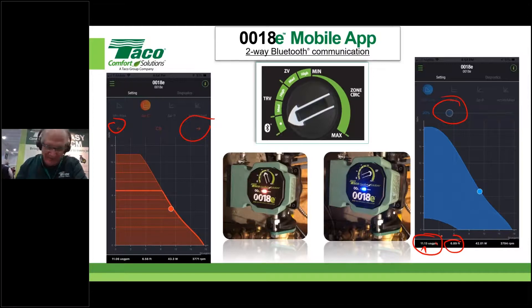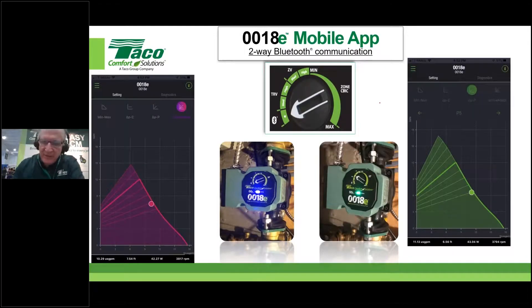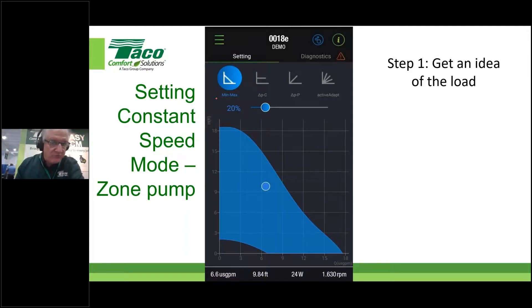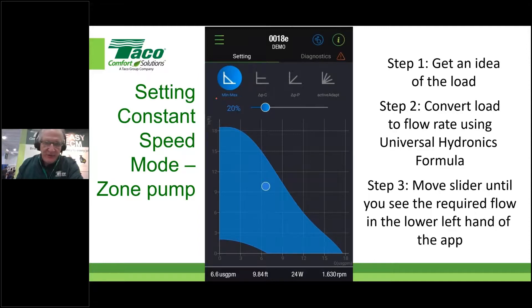There's also a constant proportional pressure mode with nine different settings selectable by finger tap, plus an automatic 'Taco Active Adapt' setting. A lot of people misunderstand what the auto function on any ECM circulator really does, and we'll cover that. To set up constant speed for a zone pump: step one, get the BTU load on that zone; step two, use the universal hydronics formula — GPM = BTUH ÷ (ΔT × 500) — to figure out the flow rate; then move the slider until you reach that flow rate.